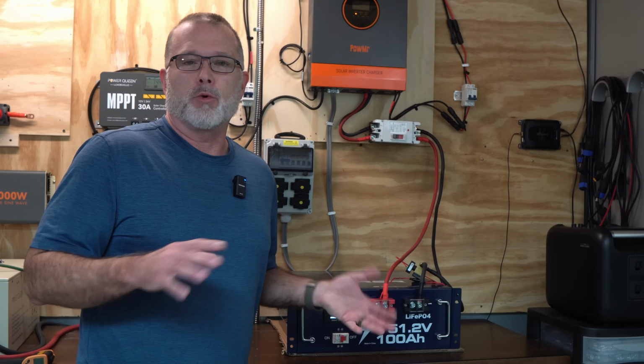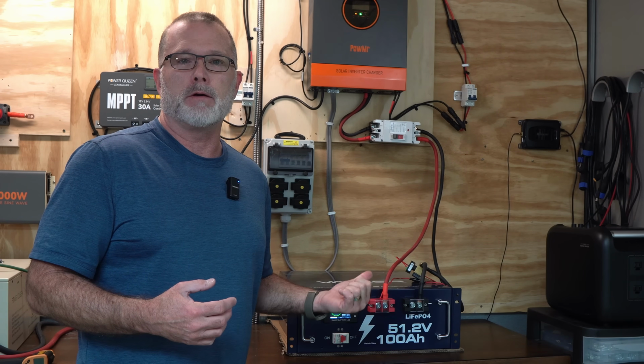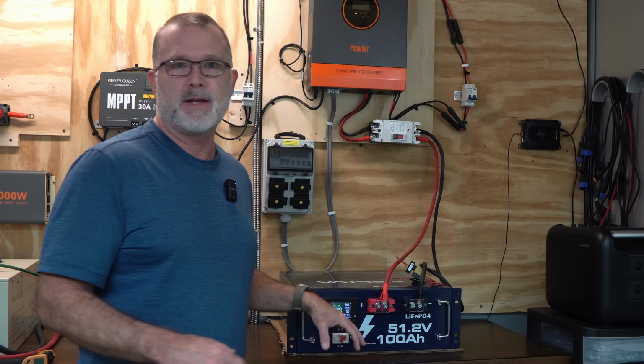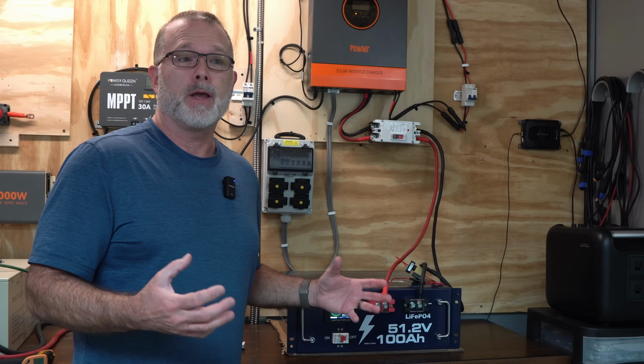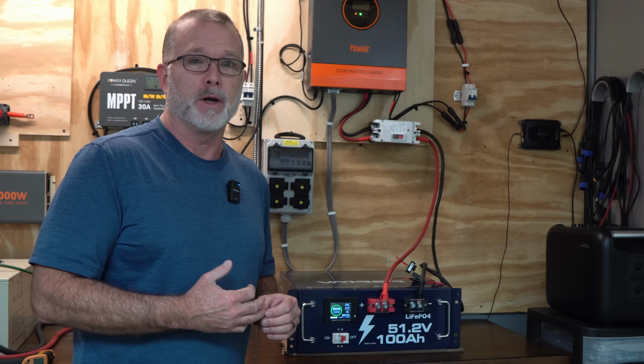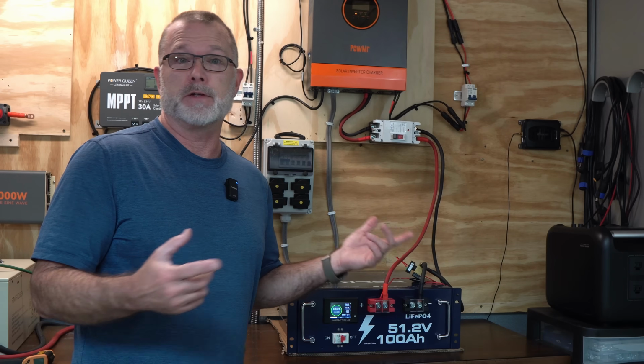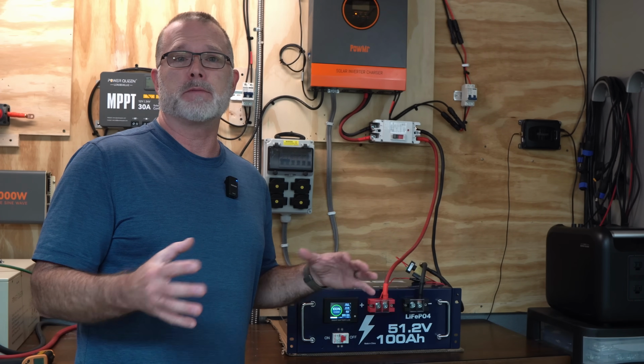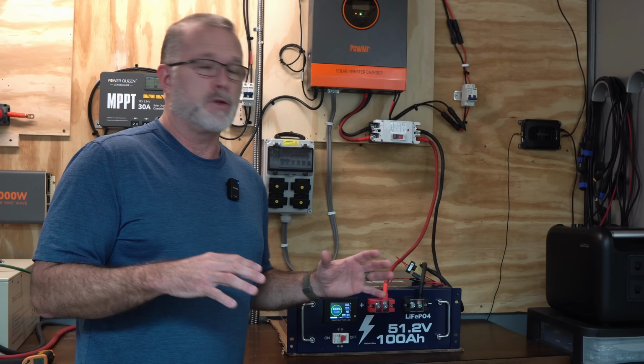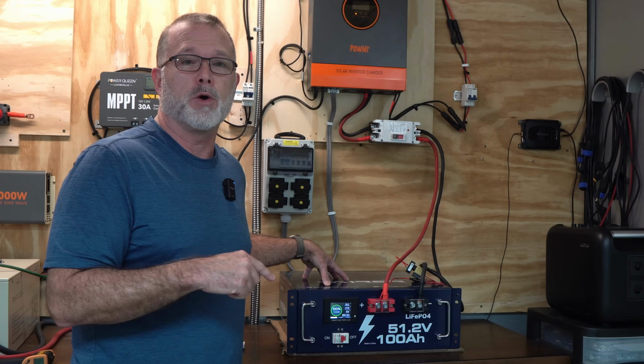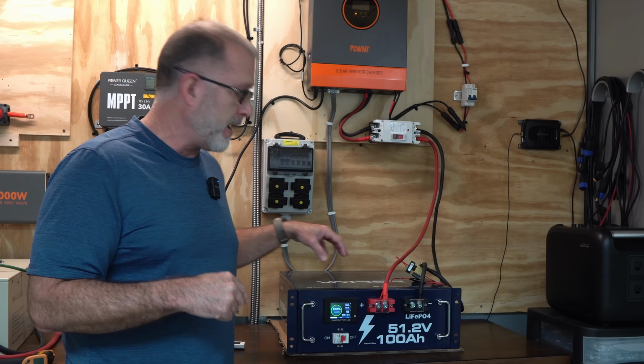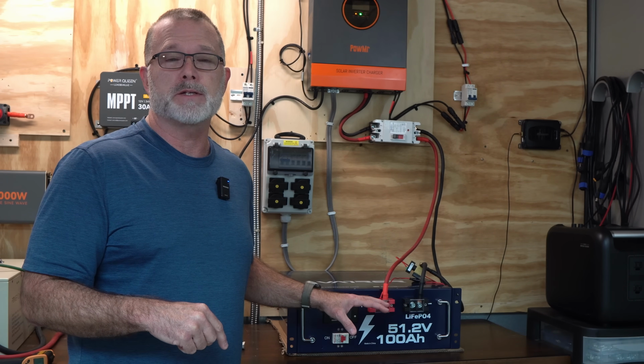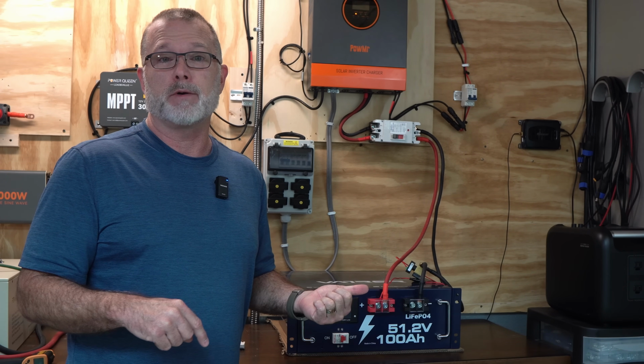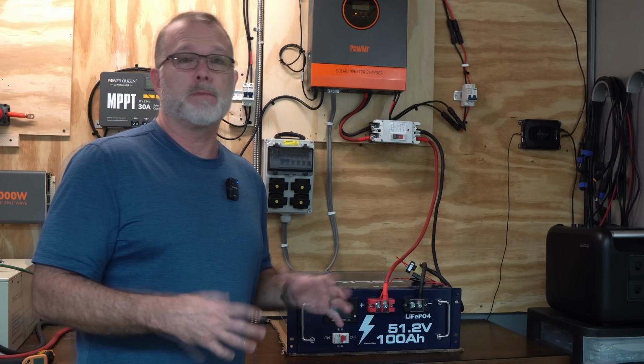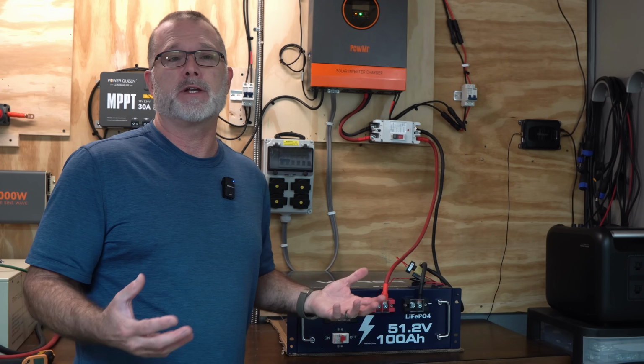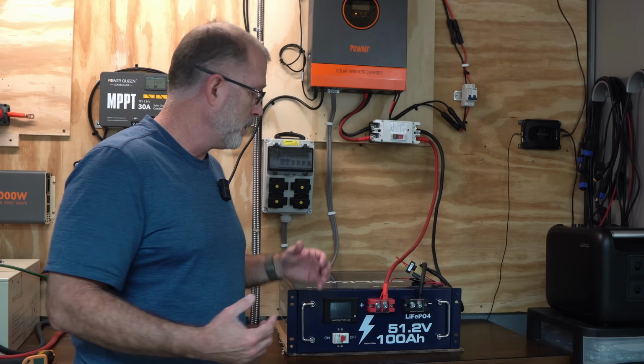Now, one other thing that I think is probably worth mentioning is that some of these 48 volt rack batteries will have an option to set up a battery ID with some DIP switches, kind of an address, and also have an RS485 comms port that you can use to connect to your inverter charger if it does support that kind of communication. And it provides some additional information monitoring to the individual rack modules within your inverter's mobile app. Now, the Vatrer Power Rack does not have that addressing or COM ports, but as an alternative, they do provide remote monitoring via Bluetooth connection to a mobile app. And you can monitor multiple batteries with that app. And that does essentially give you access to the same kinds of information, which is pretty handy.